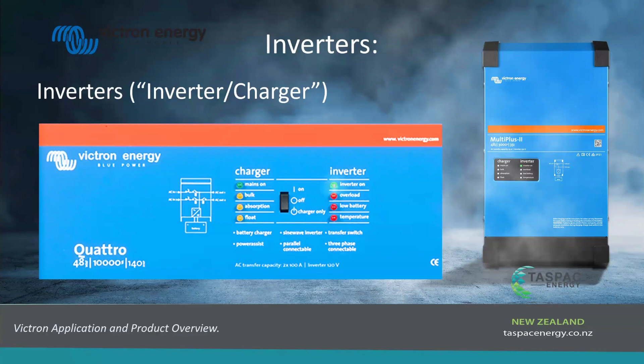So here's a Quattro inverter. There's the front cover of a Quattro inverter. Now, the Quattro inverter is a bit different, and we'll go through this shortly, but you can see the figures there, the 48, 10,000, 140. Okay, so that means it's a 48 volt battery. It's 10,000 VA or 10 kilowatts, if you want to be simple about it. And it's 140 amps capable charging current back into the battery through that inverter. You can get more charging by using the DC coupled solar, which we'll cover off shortly. And that would be charging from solar panels.